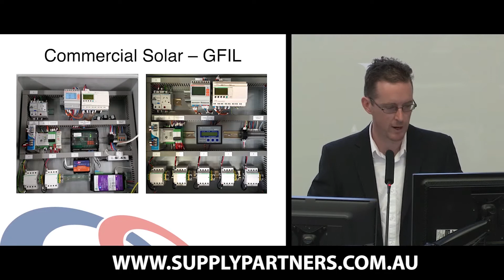Most systems in the commercial space are less than 100 kilowatts because of STCs. I've seen some people putting in 100 kVA of AC inverter capacity matched up with 99 kilowatts of DC module capacity. I think you're probably spending too much on your inverters, frankly. Aim for something like 90 kVA AC on your inverters, similar to 6 kilowatts of panels on a 5 kilowatt inverter.